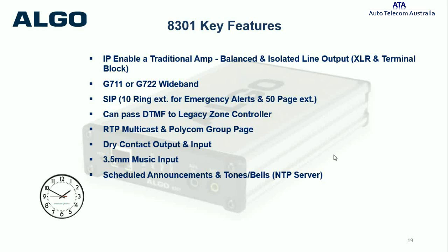SIP, you can have 10 ringing extensions and up to 50 paging extensions. You can pass DTMF through to legacy zone controllers. RTP broadcasting, and also handles Polycom paging groups. Dry contact inputs and outputs. 3.5 music on hold, scheduled announcements, tones, bells, and NTP server, etc.